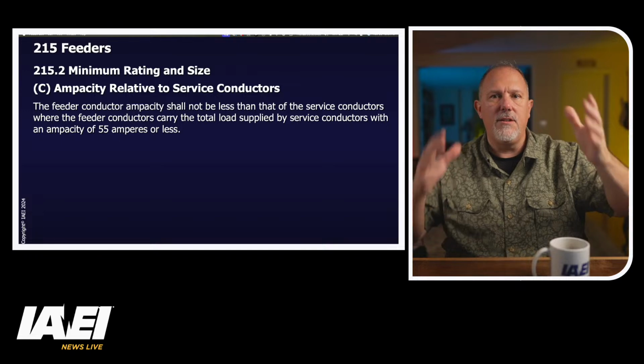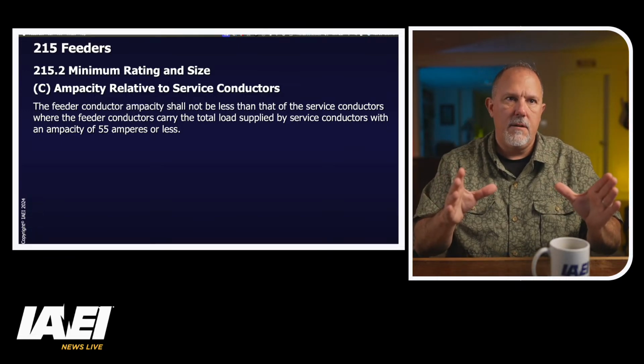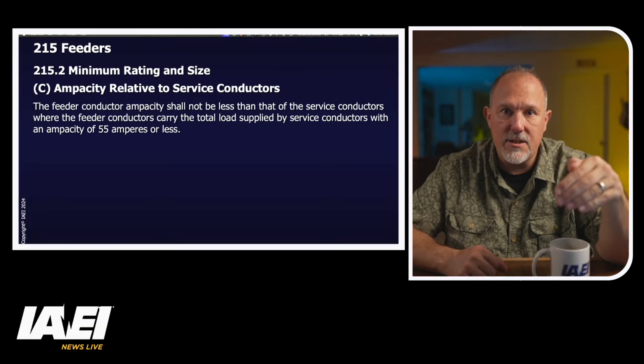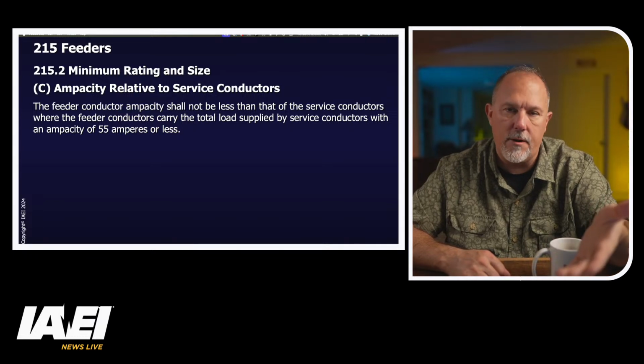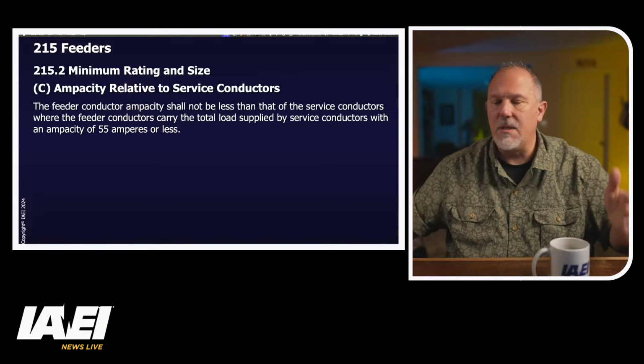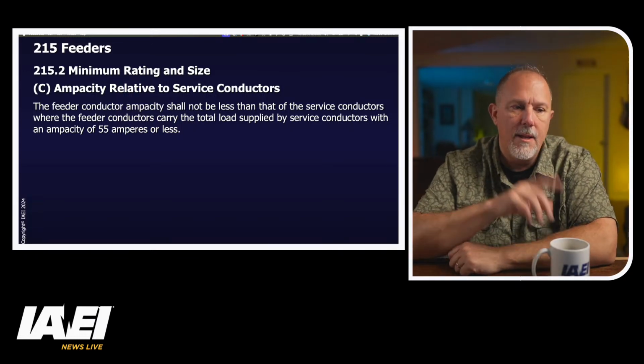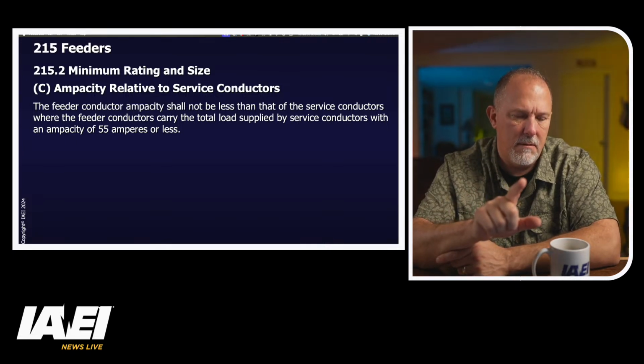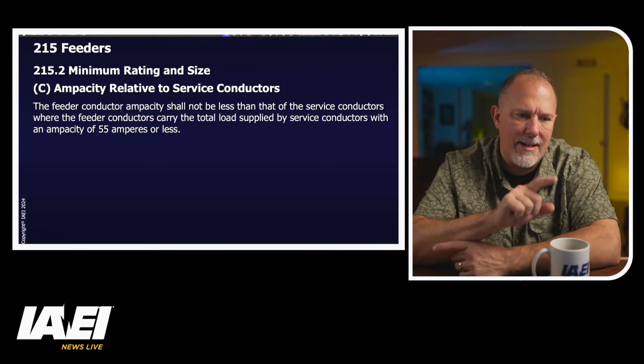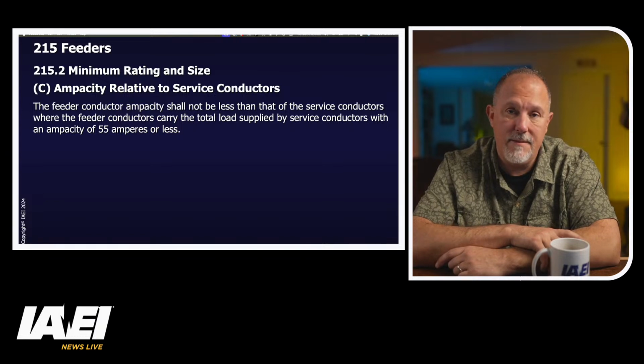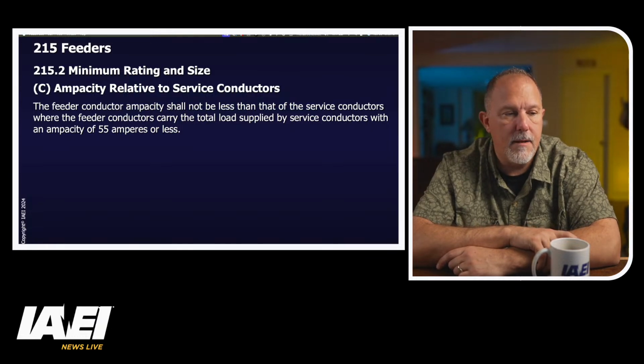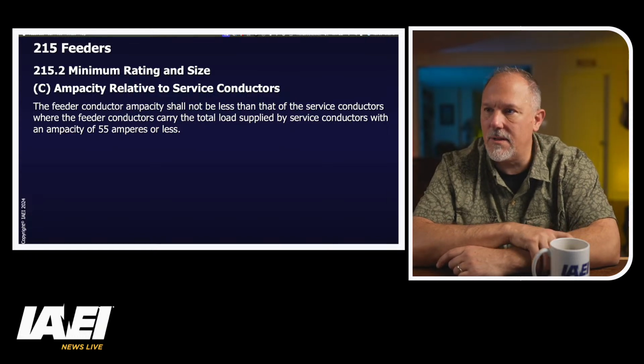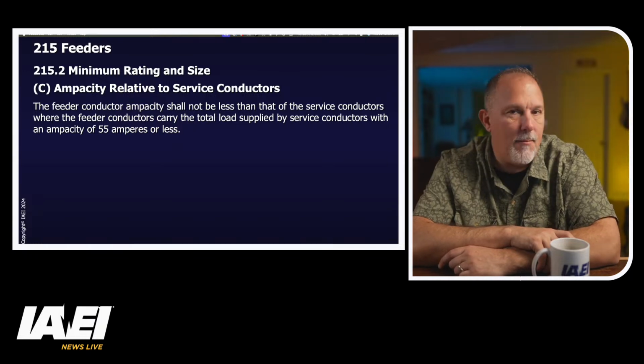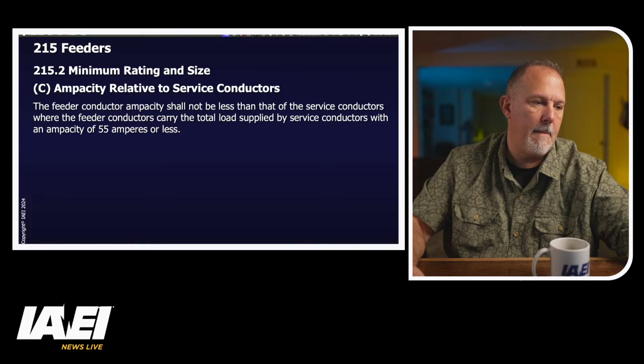So let's say I have a feeder and it lands on a service overcurrent protective device, and the service conductors coming to that device are 800 amps worth of conductor, and I'm going to land it on a 400 amp device. I could do that, and the feeder can be sized at 400 amps, which is less than the 800 amps of the service. But if my service was 55 amps or less, then I could not size my feeder at less than that, which, man, I don't understand why C is even there. I don't get it. I just don't. Because the service conductors have to have an ampacity of 55 amps or less. So I'm with you, Kawasaki. I'm with you. Yeah. All right.